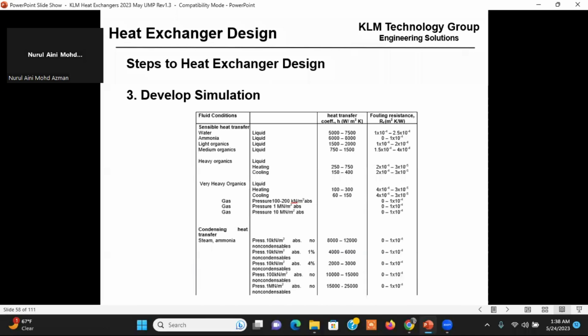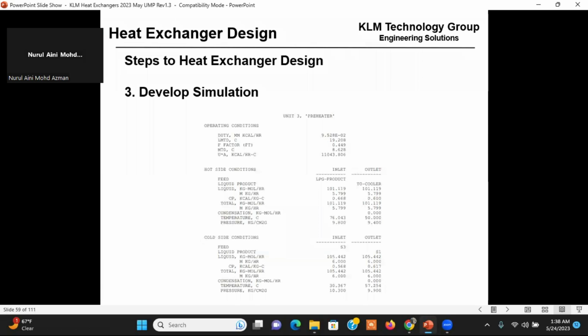And here's some more. This is out of the handbook too. Here's some more U heat transfers and fouling resistances. And so you build a simulation. And here's a converged simulation. This was the one I previously showed you, and it's got heat duties. It's got a UA there. Here's the feeds, and here's the hot side condition. Here's the cold side condition. So this was the same previous one that I just showed you for Thailand, where we built that unit in Thailand. If you develop a simulation, here's a simulation output.